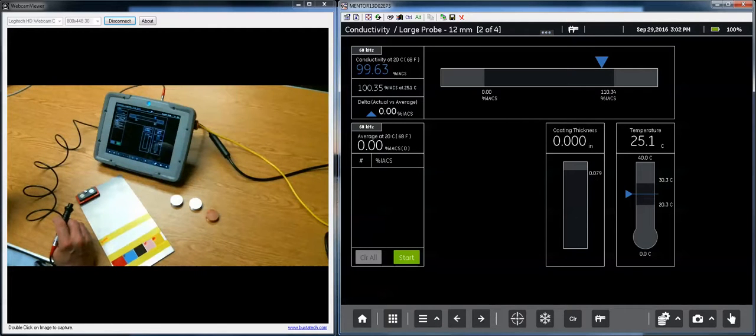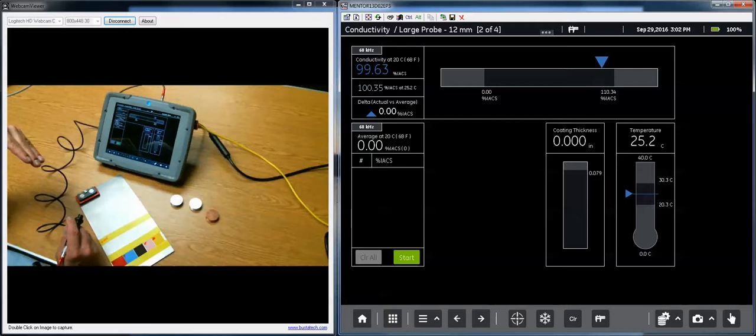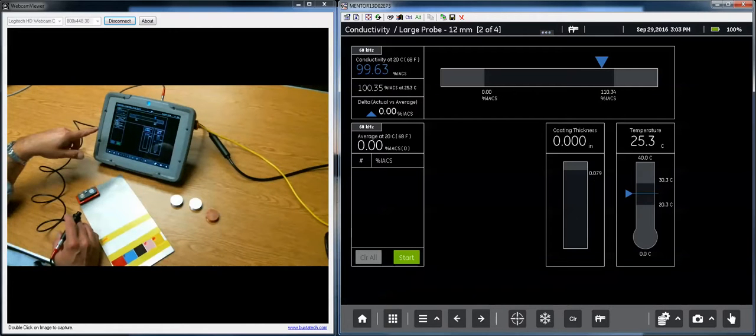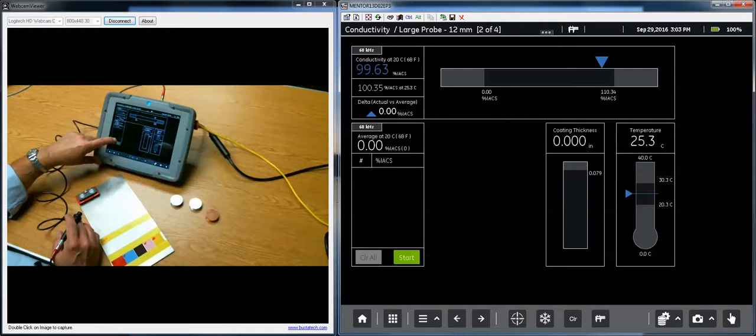You go to a known good area, you collect several samples, several measurements from known good material, you average those together, and you make that the baseline for your inspection. Then you set an alarm a little bit below that and a little bit above that. And because both Boeing and Airbus have very similar inspection procedures in this case, we try to make this easier for the inspector. So rather than having to go take a bunch of readings, write them down on a sheet of paper, drag out the calculator, and average things together, and then set the gates, we've automated all of this.